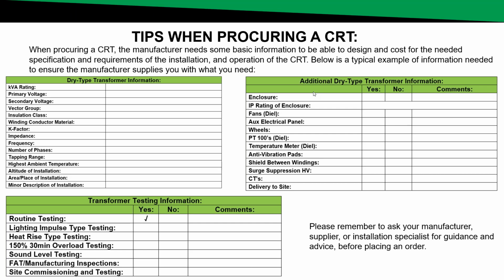Highest ambient temperature, this is quite a very important one, as cast resin transformers use natural air. So if you've got a very high ambient temperature, the cast resin transformer needs to be designed to accommodate that high ambient temperature. Altitude of installation, place/area of installation, and very important, a minor description of the installation. Is it a solar installation? Is it a nuclear installation? Is it a wind farm installation? Is it a data center installation? This will guide your manufacturer to have a better idea of what is required for your application.